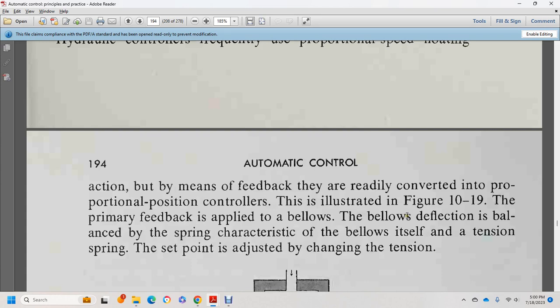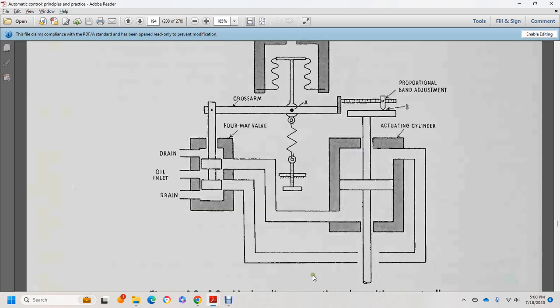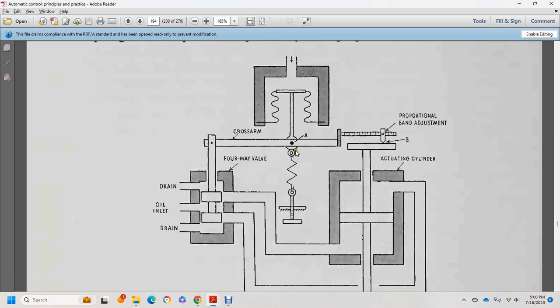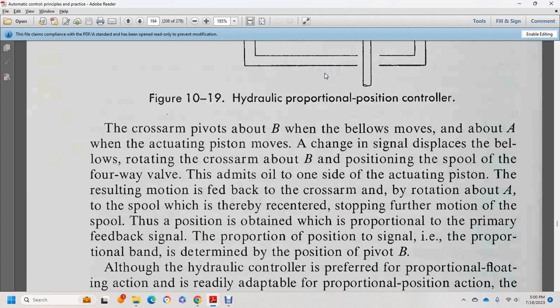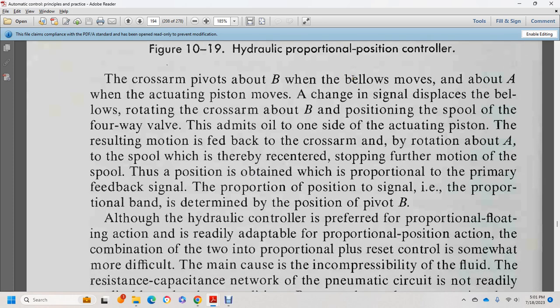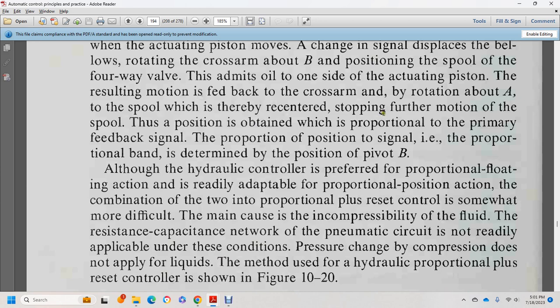A proportional speed floating hydraulic control is readily converted to proportional position control by means of feedback, as illustrated in figure 10-19. The primary feedback is supplied by bellows, with spring tension adjusted for the set point. Components include: hydraulic proportional-position controller, actuating cylinder, drain, oil inlet, four-way valve, cross-arm, and proportional band adjustment. The cross-arm pivots about B; as the bellows moves about A and the actuating piston moves, the cross-arm rotates, repositioning the spool and resetting the spring. The proportional band is determined by the pivot position B. Hydraulic proportional plus reset control is described in figure 10-20, though it is more difficult to implement than proportional floating action.